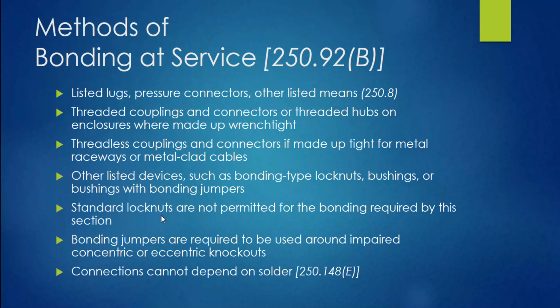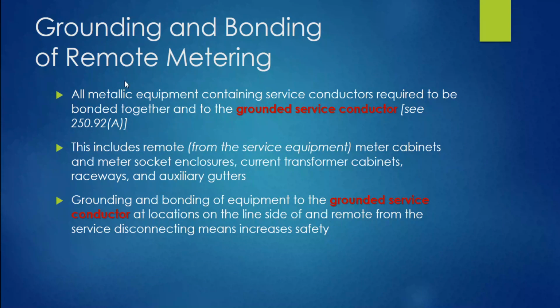Again, reminder, standard lock nuts are not permitted for bonding on the supply side or line side application. Bonding jumpers are required to be used around impaired concentric or eccentric knockouts. Eventually, I'll know that I'm pronouncing that right. And connections cannot depend on solder. You cannot do all this in lieu of all this by soldering pieces together. Not acceptable. Now, let's talk about grounding at remote meters.